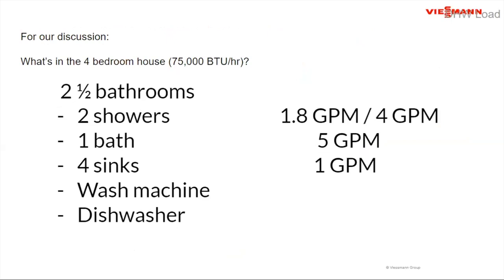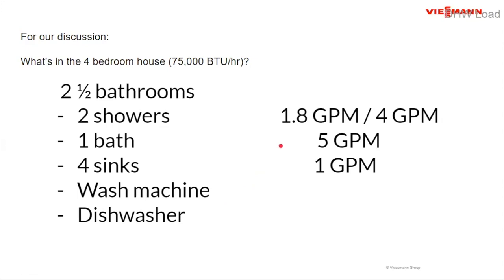We know from looking at the plans of the house what the water heating needs are. So this is a four-bedroom house, again, 75,000 BTUs per hour, and it has 2.5 bathrooms. Among these 2.5 bathrooms, there are 2 showers, 1 bath, 4 sinks, 1 washing machine, and 1 dishwasher. And each one of these represents a hot water loading. To the right-hand side, I have a couple of items that are listed in gallons per minute. We look at the hot water usage. Sometimes we talk in gallons per minute. Sometimes we talk in gallons per hour. That's important when we look at the water heating methodology. But this is what we really have to work up against.